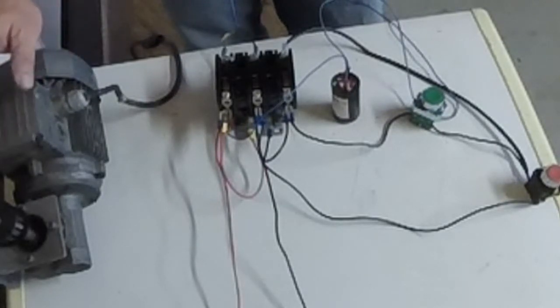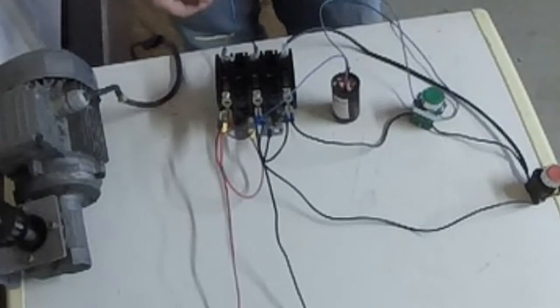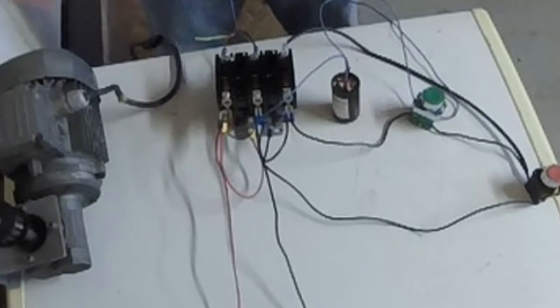This is a European motor. So the wiring is such that it has a black wire, a brown wire and a blue wire. In North American wiring, we generally omit the blue wire or put another power pole to it. It is not neutral here in the United States.